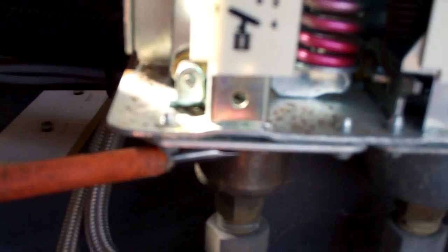These work with little bellows here. That's your high pressure one, that's your low pressure one. That's normally closed and that one's normally open. So pressure on that one going up will make the switch open. Pressure on this one going up will make the switch close.